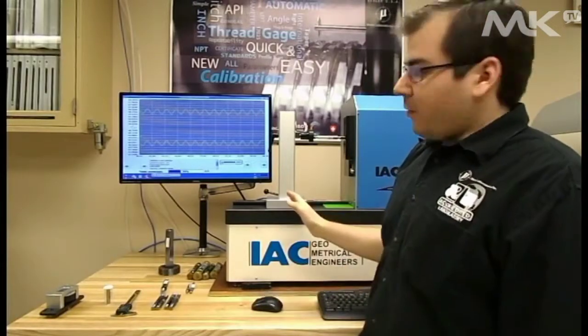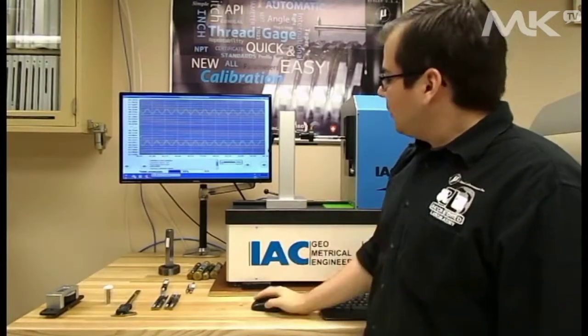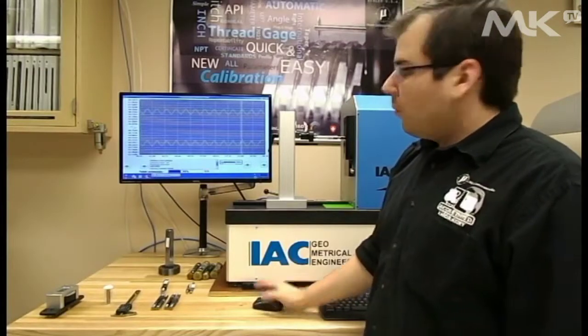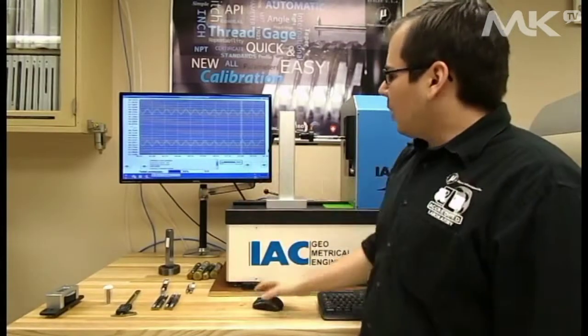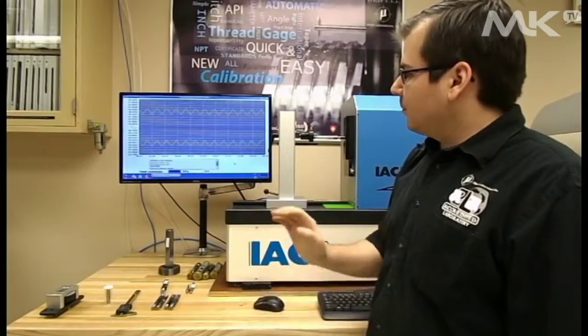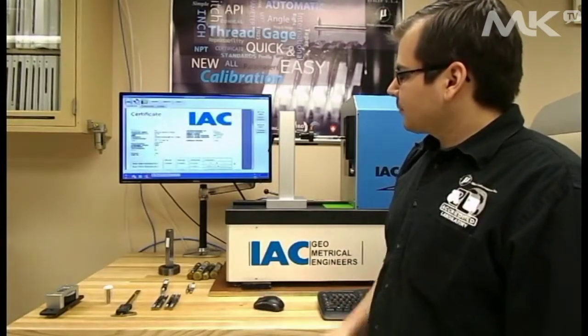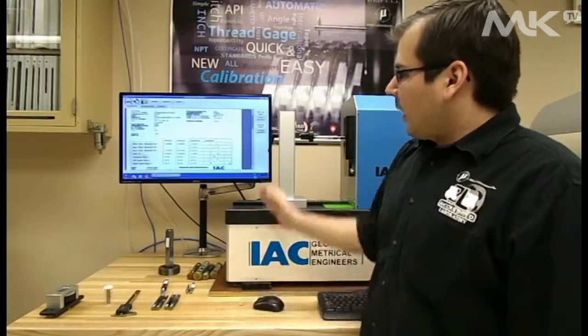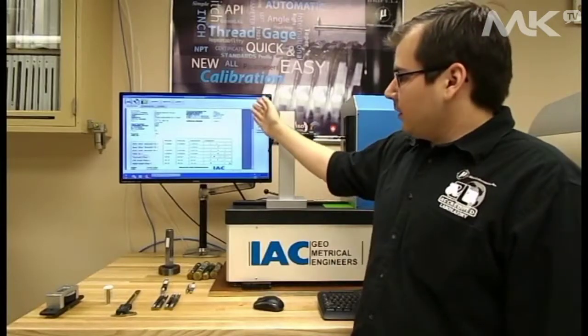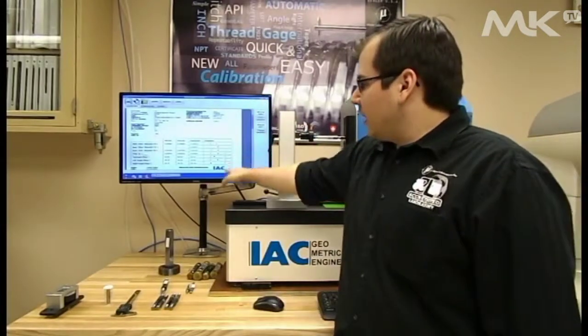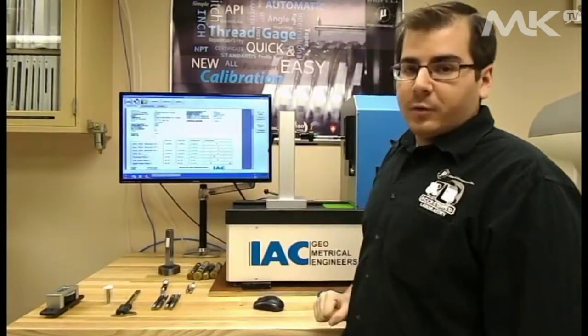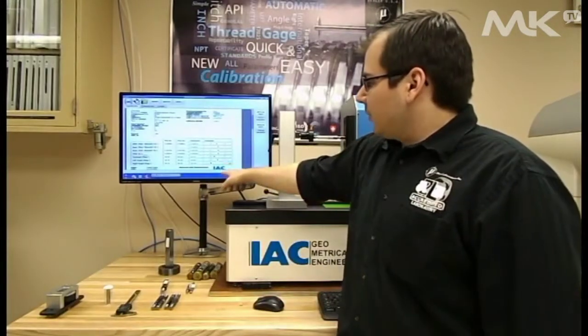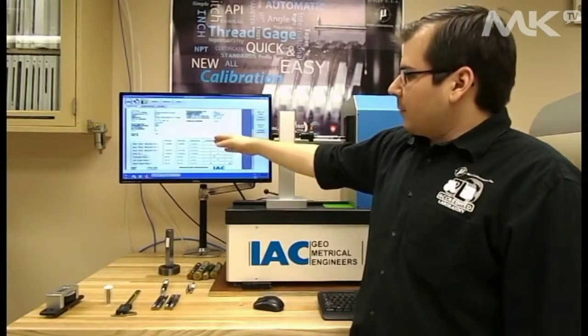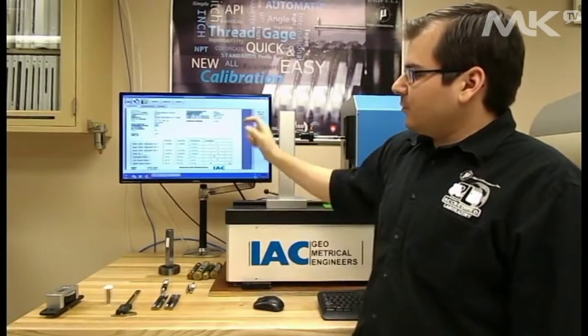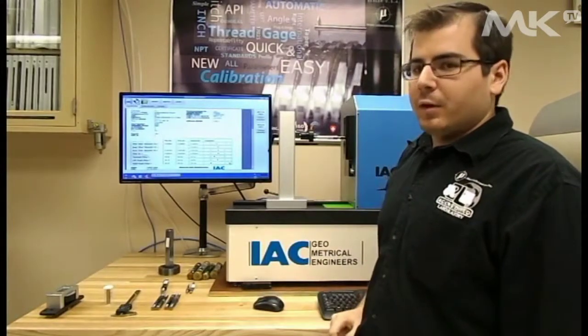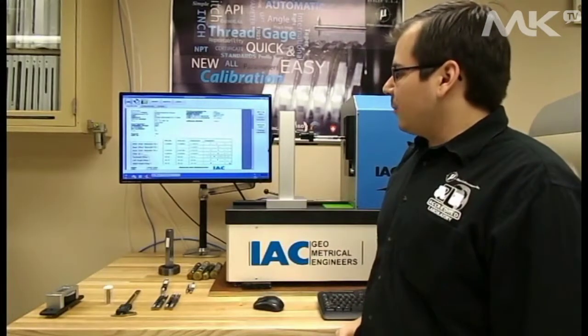So just to make sure we don't fail a gauge based upon the front, we'll bring the measurement line in. Cut off a few threads and hit continue. And as we defined earlier, the MasterScanner cert actually draws lines where the tolerance boundaries are and puts data points for basic major, minor, basic pitch, top angle, left angle, and right angle. And as you can see, this gauge passes.